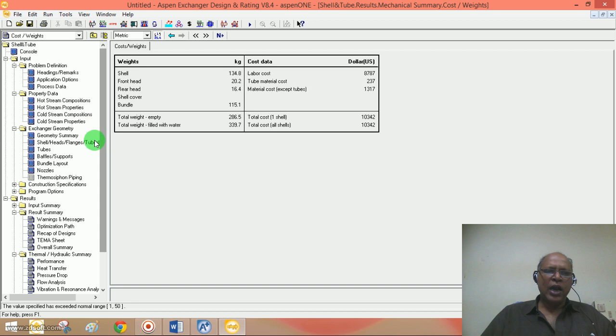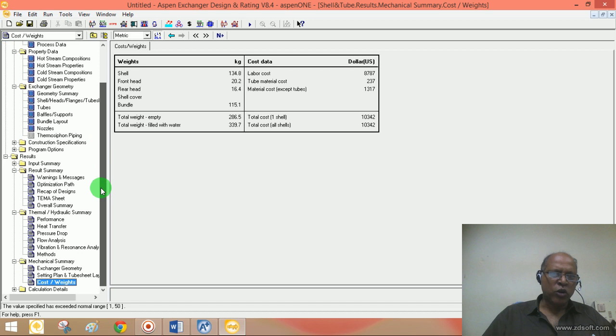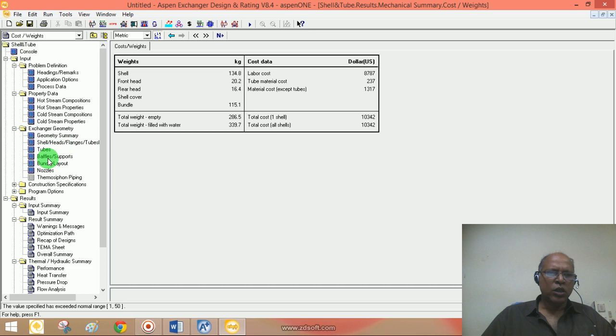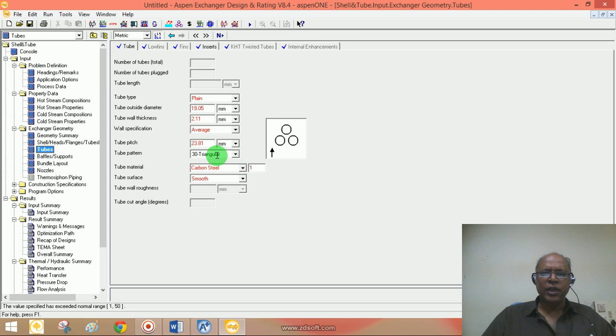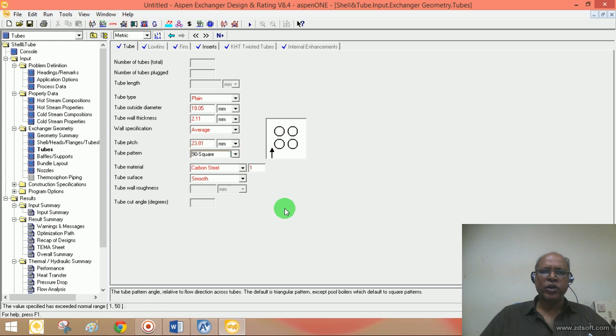I request students to go into each and every detail to identify what is happening and whether you can make modifications or see how the calculations are actually done. I'd like to make one or two simple changes to show the possible effect on the design. Going to the input, under Geometry > Tubes, earlier we were using a 30° triangular pitch — I would like to change it to 90° square pitch. This is the only change I will make.